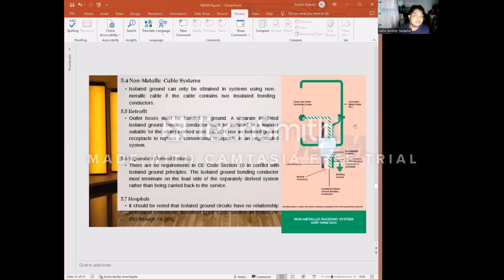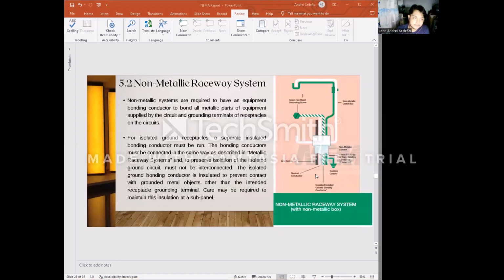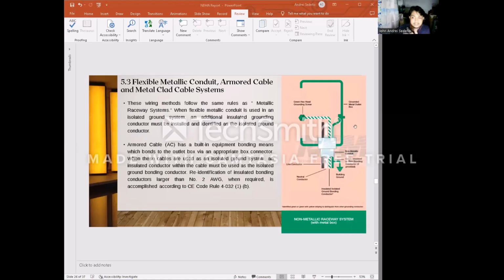Now, for the non-metallic cable system, an isolated ground can only be obtained in a system using non-metallic cable if the cable contains two insulated bonding conductors. And in addition pala, the difference between this flexible cable versus armored cable is that armored electrical cable has an extra layer of armor compared to the ordinary flexible cable. There are steel tape armor, thin steel wire armor, and thick steel wire armor. Armored cables are more suitable for direct burial than ordinary cables, with a stronger mechanical resistance. So mas matibay siya.